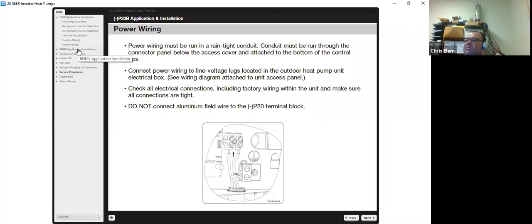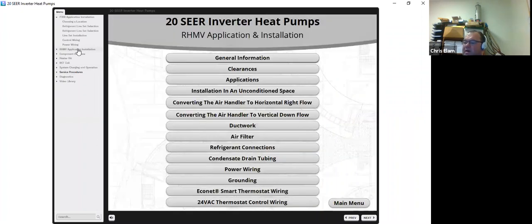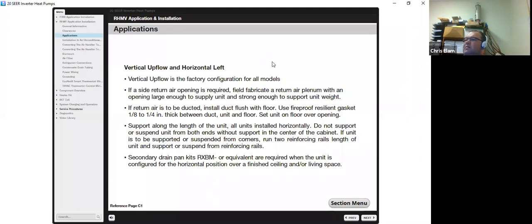So this is a two-part webinar series on these units. We're going to jump into the RHMV air handlers now. This is Rheem's communicating air handler, which is designed to match these units. For installation, you have 4 options. You have vertical upflow and horizontal left. Vertical upflow is out of the box. You also have horizontal right and downflow as well.